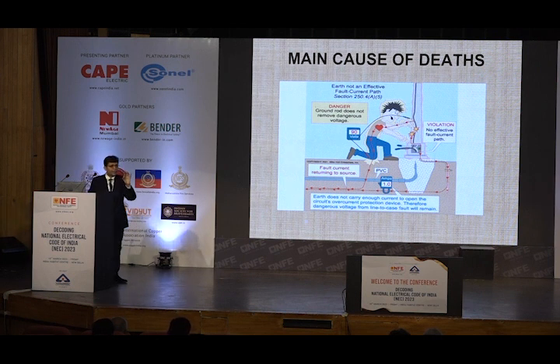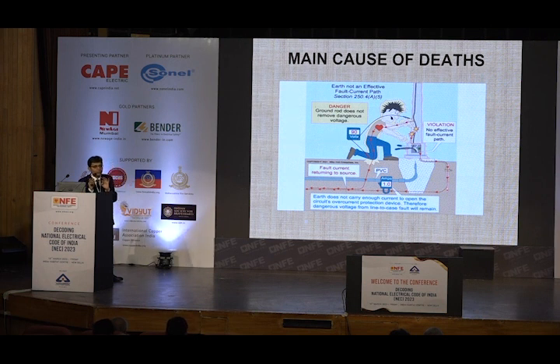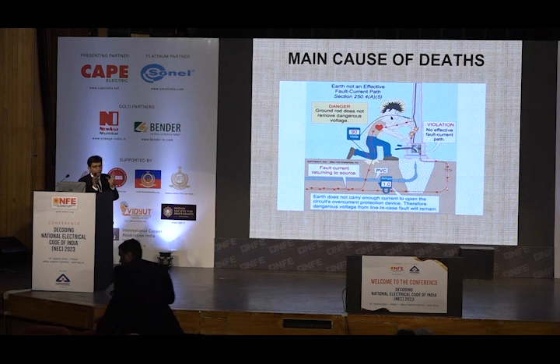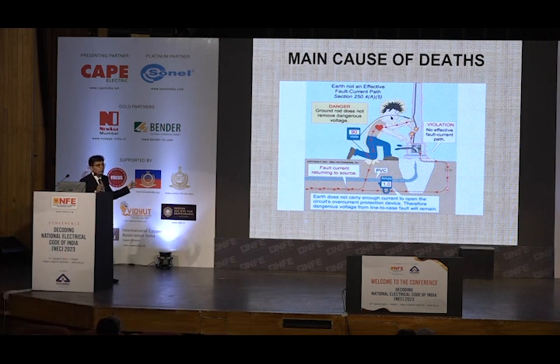This picture depicts one thing, that merely connecting your system to earth is not going to protect you. If you haven't provided a dedicated path for that fault current to go back to the source, your earthing won't ensure that you are not going to get a shock. Because to get a shock, 30 milliamperes is sufficient. And that depends on your position and on the values offered by your earthing system. Talking about 1 ohm, 2 ohm is irrelevant. You have to provide a particular earthing system so that your fault current can reach your source in the minimum possible time. That ensures safety.